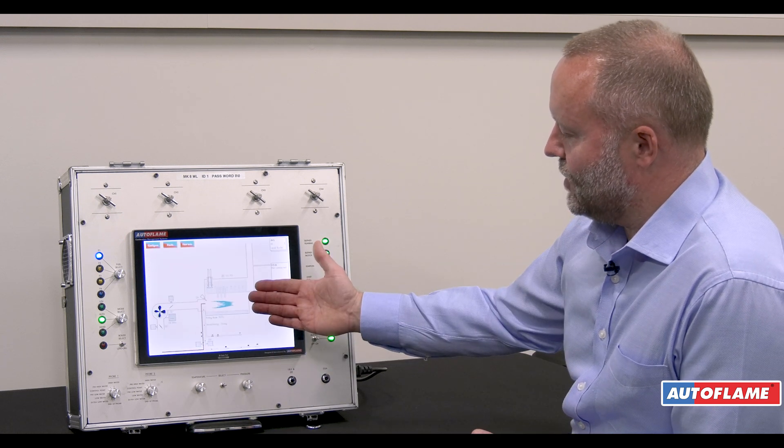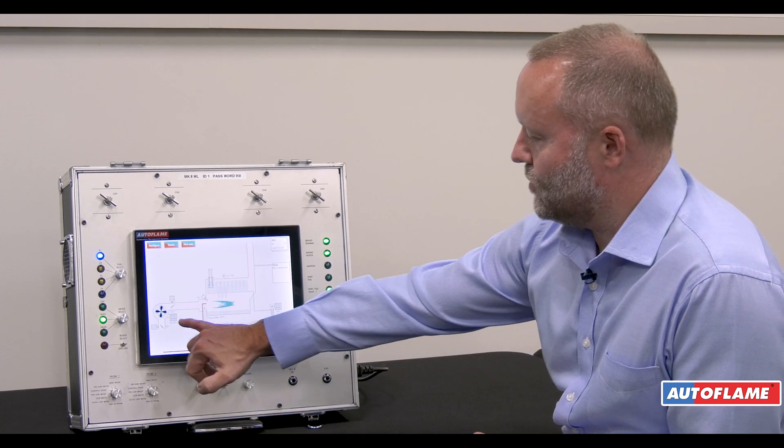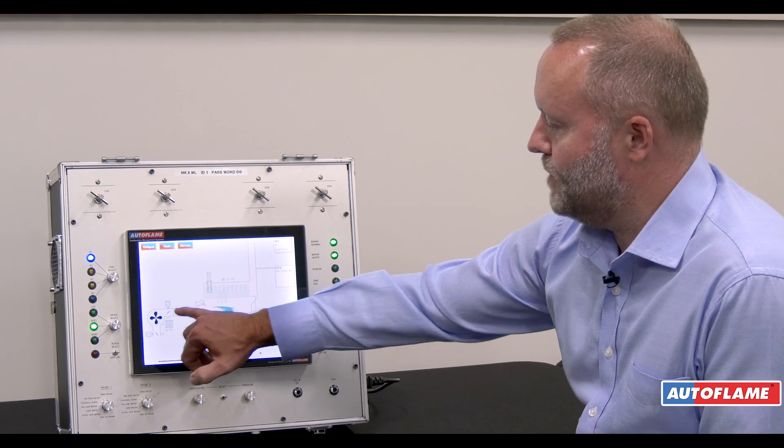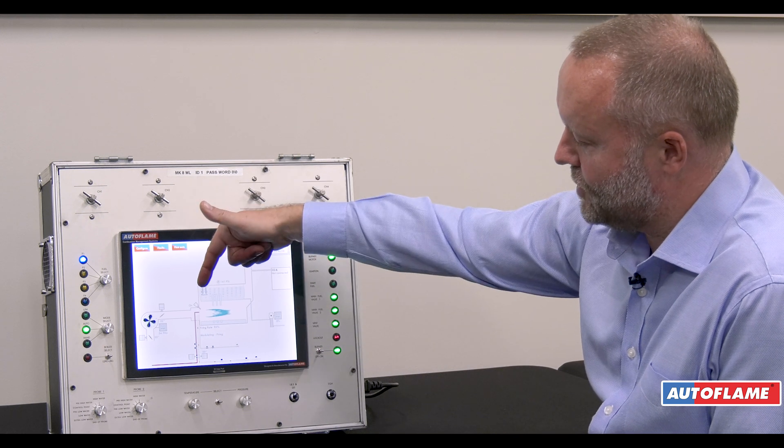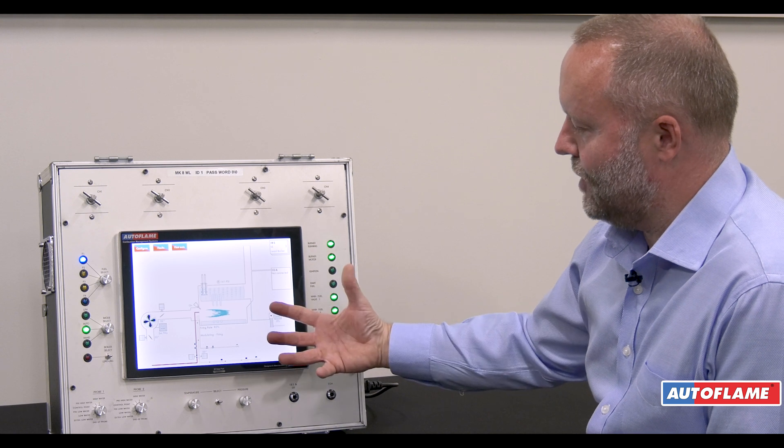In that type of application we add meters to the gas and also the air. Now these meters can either be mass flow or just a volume meter. If it's a volume meter we'd then need to measure the temperature of the combustion air and the natural gas and also the pressure, giving us a mass flow.